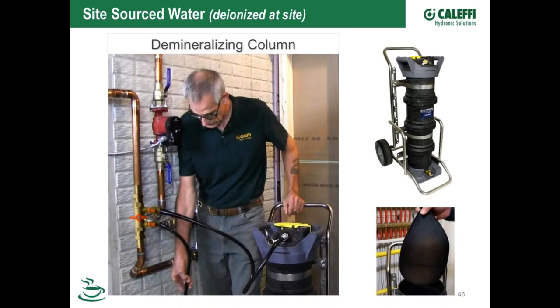The reason the pH even drops is that when water comes out of a demineralizer, it's looking for carbon dioxide. If you take a long time to fill your system up, that demineralized water has time to absorb carbon dioxide and create a slight acid called carbonic acid, and your pH will drop down a little bit.